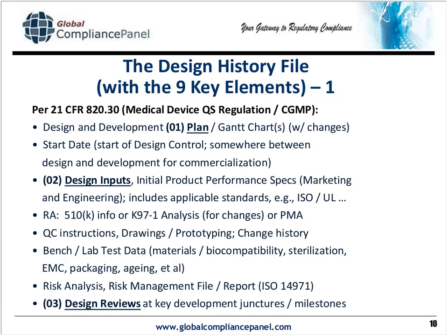Or I recommend that in order to do that analysis, you go to the FDA's website, look for their K97-1 memo for changes. They had a draft guidance document out on changes, but they pulled that. But basically, the K97-1 gives the same kind of information. I usually make a matrix out of that K97-1, every single element on it, and then I go through it each time there's a major change as part of the change order.